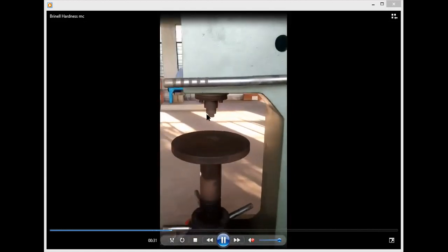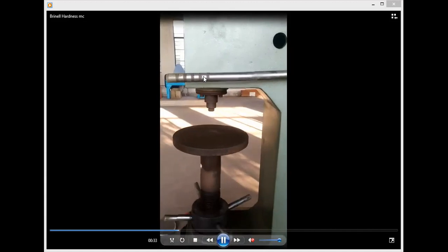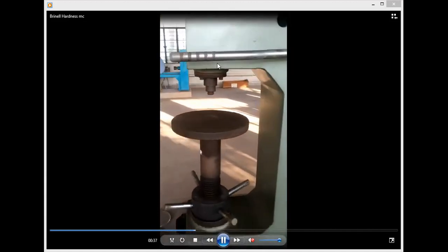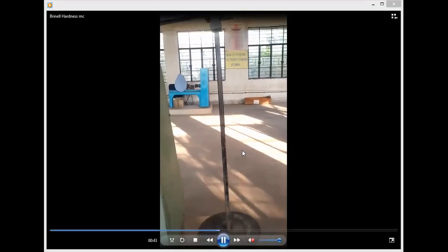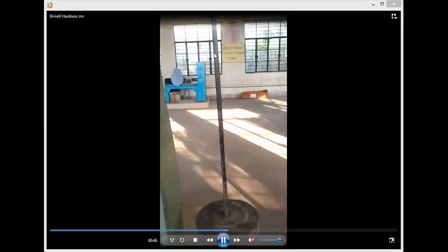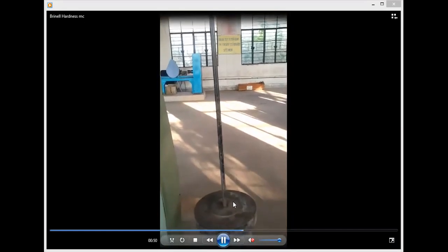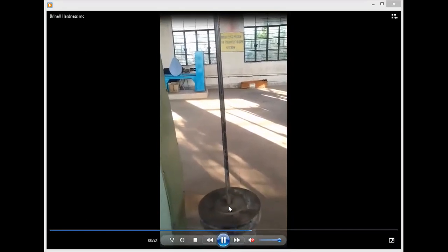Here we will fix the indenters. This is the rod which in this present position is in the unloaded position, and if we move it to the right, it will load the indenter onto the work itself. This is the load carrying hanger, whose equivalent load in this form is equal to 500 kgf, equivalent not equal to.